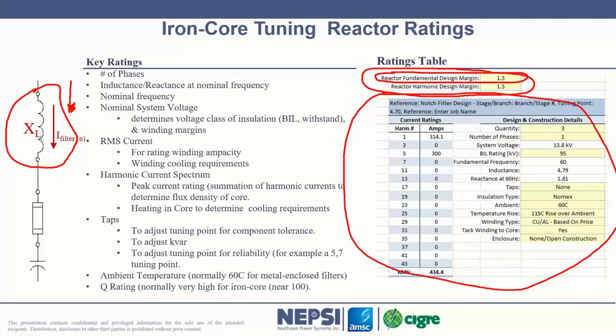This is our philosophy: multiply the fundamental by 1.5. Do we always do that? No. But if it's a harmonic filter going into a process industry where we're looking for high reliability, we're multiplying the fundamental current by 1.5, despite the fact that you will only have a 10% over voltage in the system, and it will result in that 1.5 per unit.